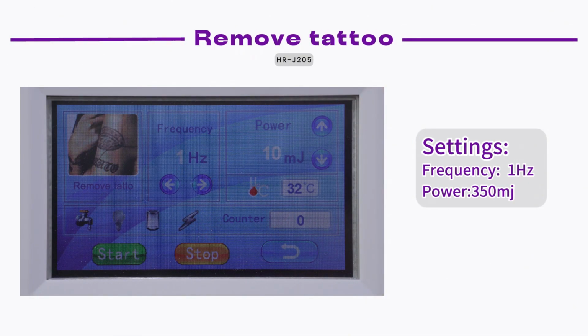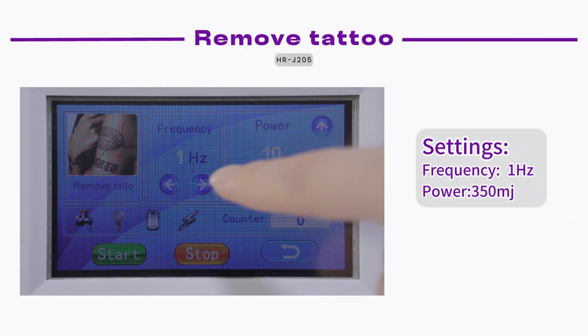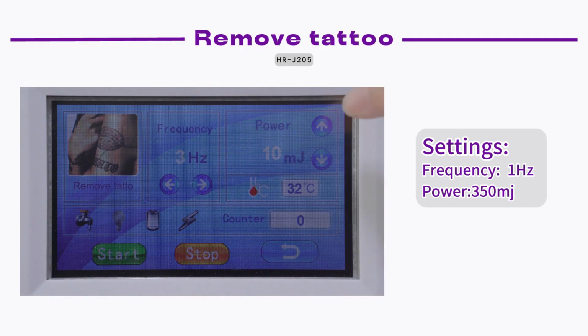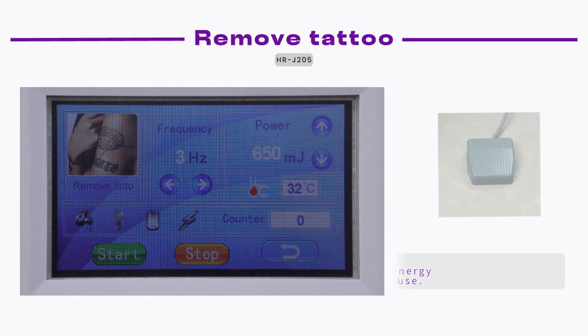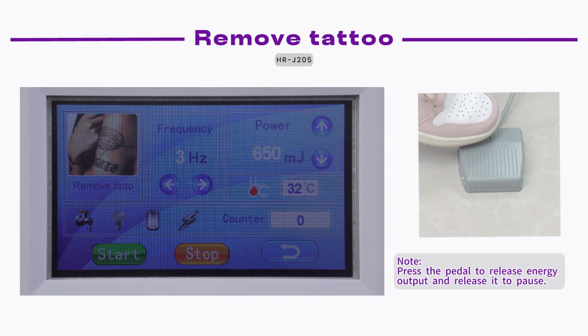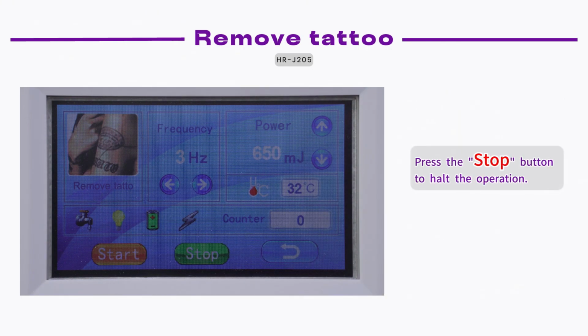Choose Remove Tattoo. Settings. Frequency, 3 Hz. Power, 650 mJ. Note, press the pedal to release energy output and release it to pause. Press the start button to start the process. Press the stop button to halt the operation.